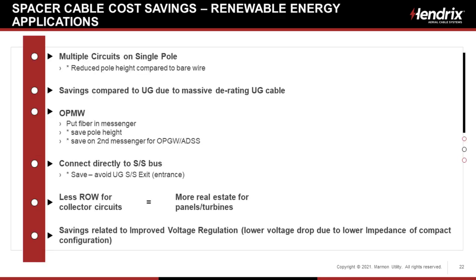We're going to be able to put multiple circuits on a single pole. Here's the savings, and I'm going to just blurt through these now, and we'll go through them in intricate detail later. But multiple circuits on a pole, we're going to have savings compared to underground due to massive derating of those cables. OPMW, boom, we're going to put the fiber right in the messenger, save 5 foot on the pole. We're going to connect directly to the substation bus rather than having those costly and messy underground substation exits.